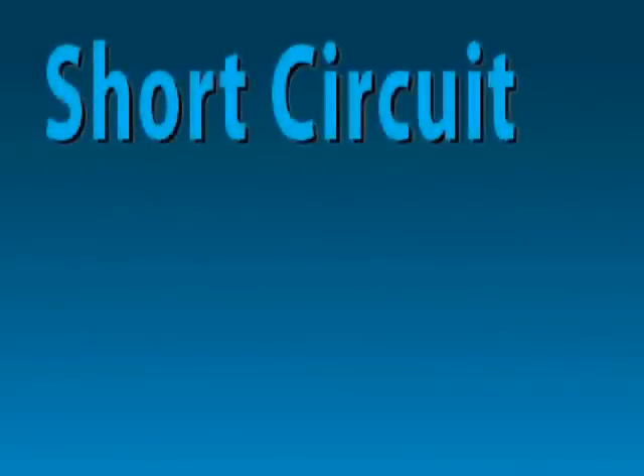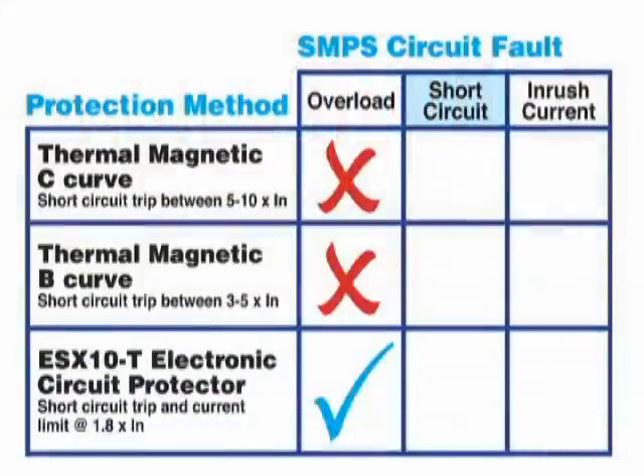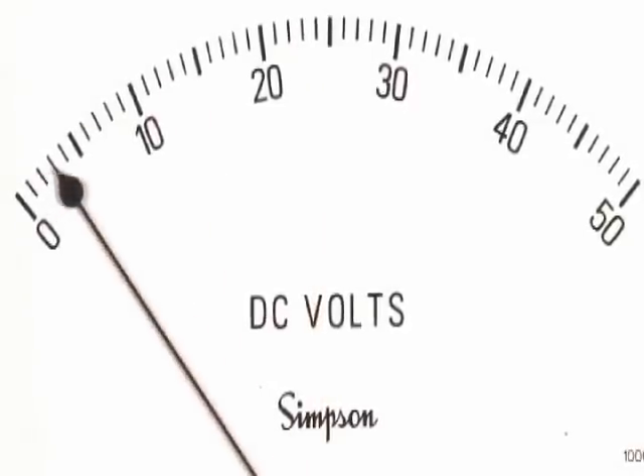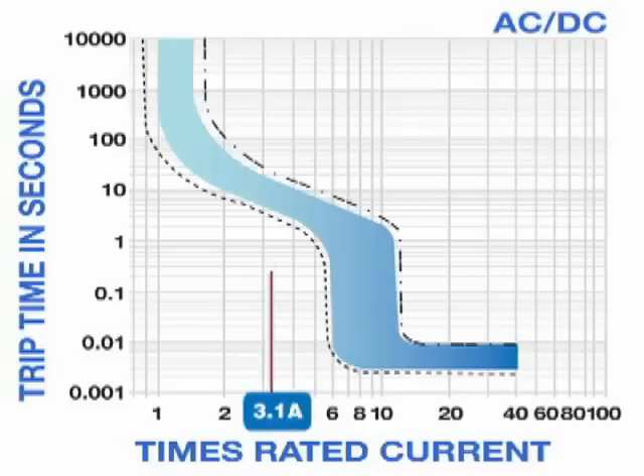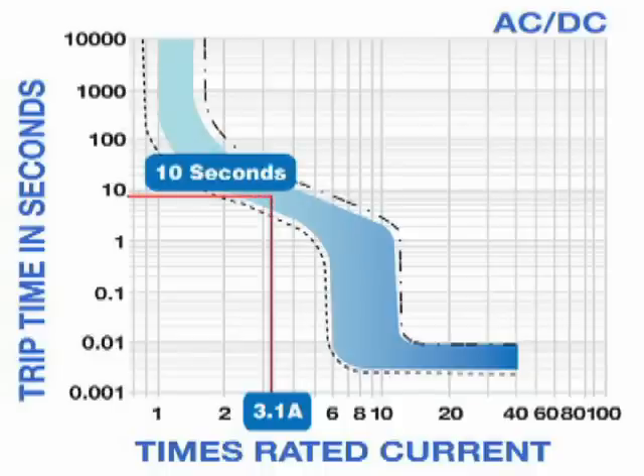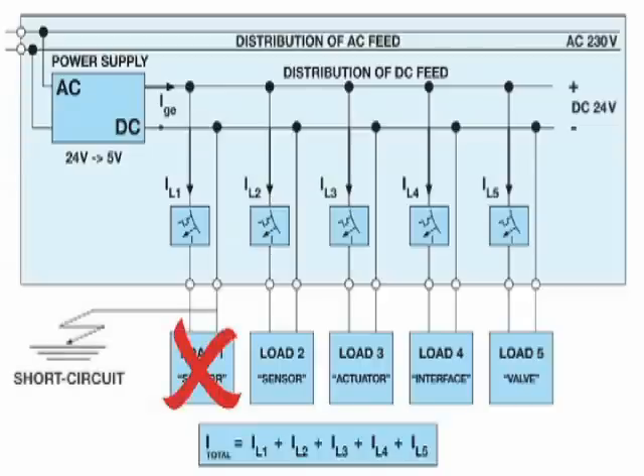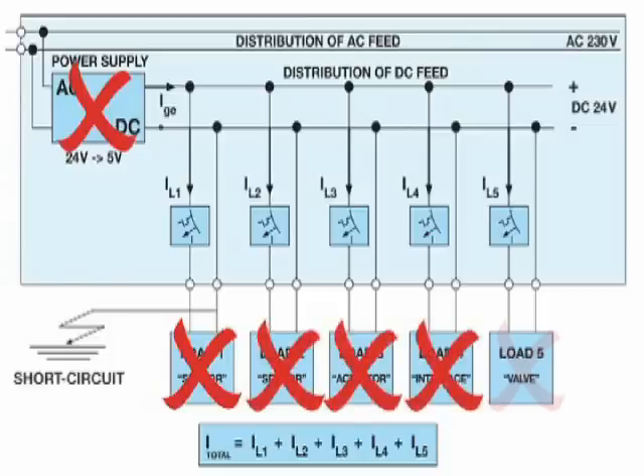Our second condition is a short circuit. Now let's simulate a worst case short circuit with the three types of protection methods. Notice the short circuit current at greater than three amps and the 24 volt DC drops to under five volts DC to protect the power supply. The C characteristic circuit breaker did not interrupt the short circuit instantly because it requires at least six times the rated current — six amps — to activate the magnetic trip. The switch mode power supply cannot generate enough current boost to trip the circuit breaker, compromising the integrity of the system. Any additional loads have lost 24 volts DC and it will take the breaker approximately five to ten seconds to disconnect the faulty circuit and restore 24 volts DC.